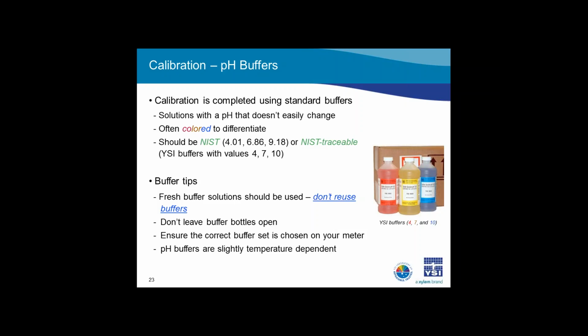It is also important to note that pH buffers are slightly temperature dependent, so the actual pH value of the buffer varies with temperature. For example, the actual pH of YSI buffer 7 at 20 degrees C is 7.02, and at 25 degrees C, it is 7.00. pH buffer values based on temperature can usually be found on the bottle or certificate from the buffer manufacturer. For maximum accuracy in your pH measurements, be sure that the auto buffer recognition is adjusting the buffer value based on temperature, or override the calibration value with the correct temperature adjusted value. All YSI lab and field instruments have buffer values based on temperature pre-programmed into the instrument software in the auto buffer recognition feature, and these temperature corrected values are used.